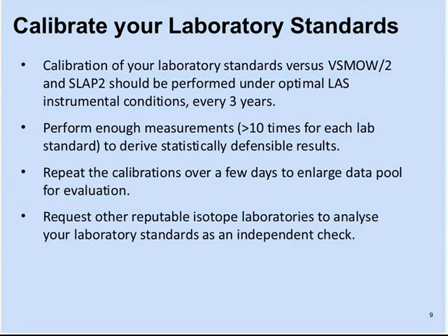You need to perform enough measurements, I would say again, at least 10 times for each of the standards to get statistically defensible results. You probably want to repeat this calibration over a few days just to enlarge the data pool for evaluation. And, of course, many laboratories are more than happy to assist. So if you've prepared a laboratory standard and you're not sure if you're getting good results, you can send it to the agency. I'm sure there are other laboratories that would be more than happy to run it as an independent check.